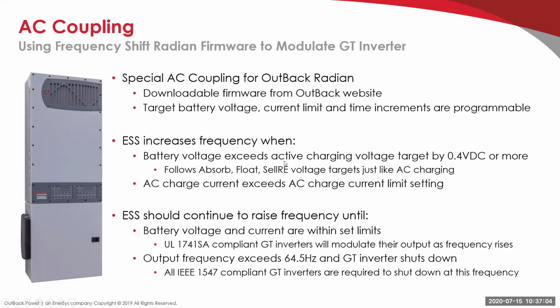And then when the battery voltage exceeds the active charging voltage by more than 0.4 volts, whether that's the absorb, the float, or the SellRE, depending on which target is active, it's going to start increasing the frequency. On the older UL 1741 or IEEE 1547 inverters, at 60.5 they'll just shut down, go offline. Then the Radian inverter will power the loads until the batteries go down, and then the grid tie inverter will come back on. They'll start powering the backup load panel along with Radian, or if there's extra energy, it's going to come back on and charge the batteries again. And if the batteries get too high, then we protect it.